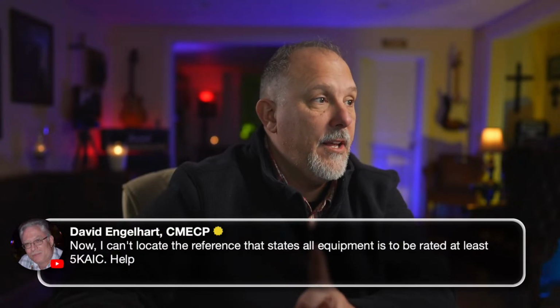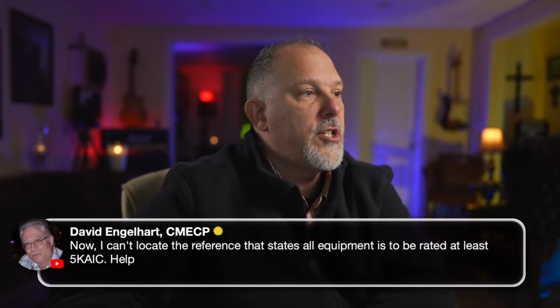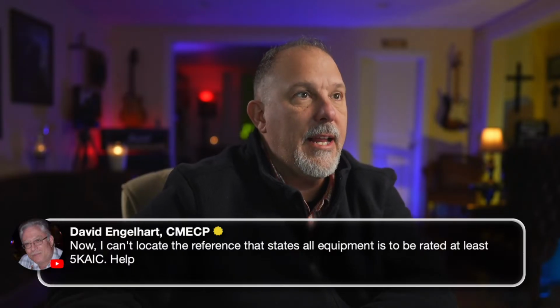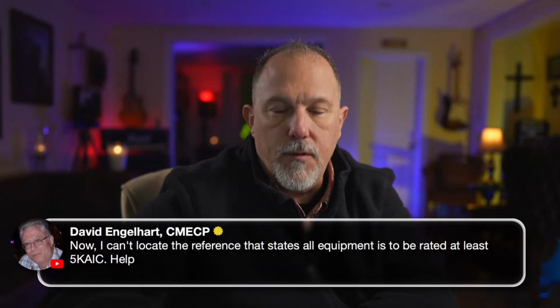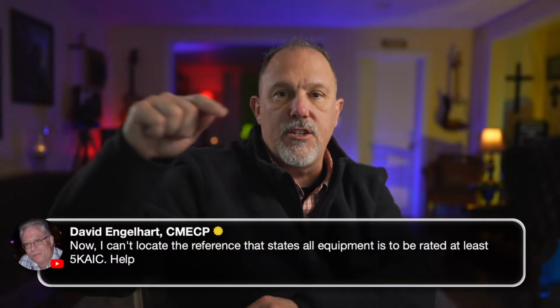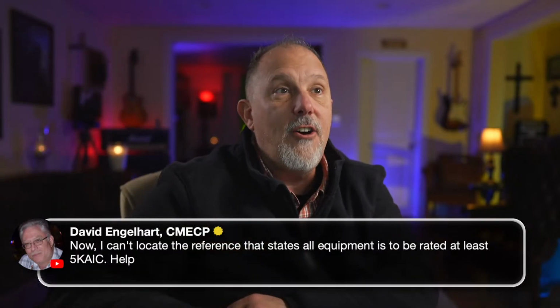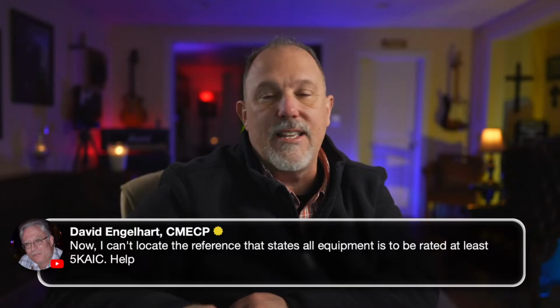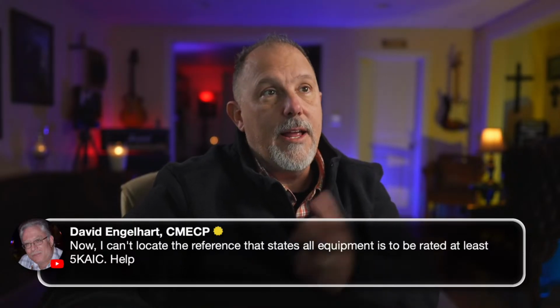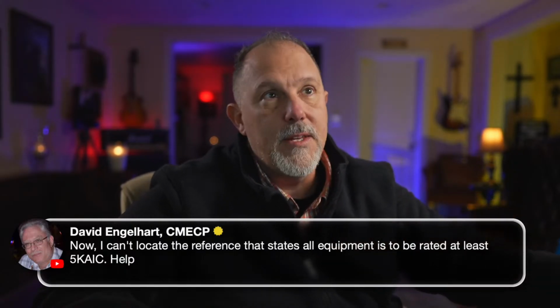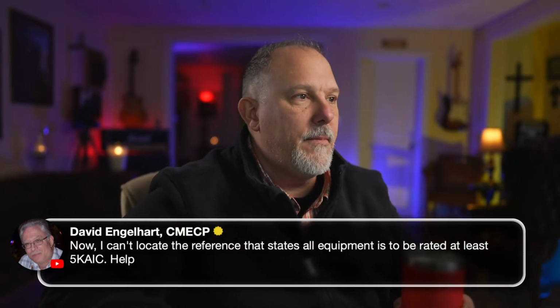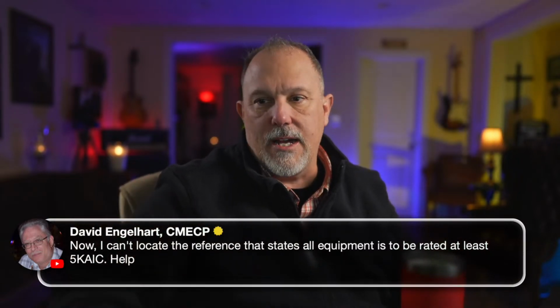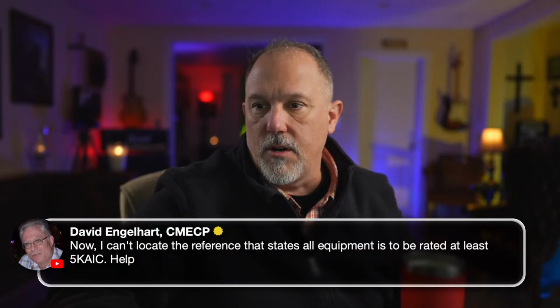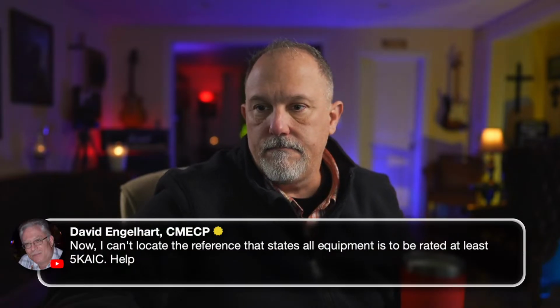240.16 is in part 1. So we added 240.16, interrupting ratings, and we said overcurrent protective devices specified in 240.7 shall have an interrupting rating not less than 5,000 amps. And that would include the fuses. So we lost the 10,000 amp default for unmarked fuses. But that's okay.